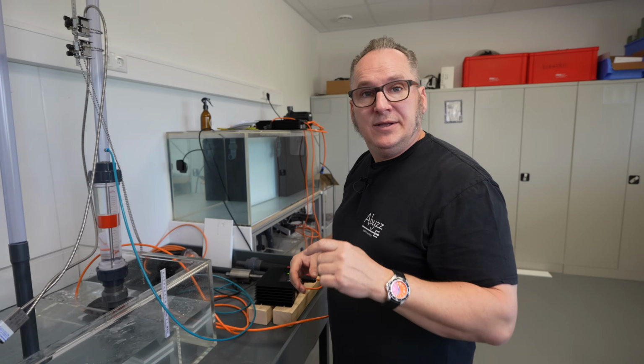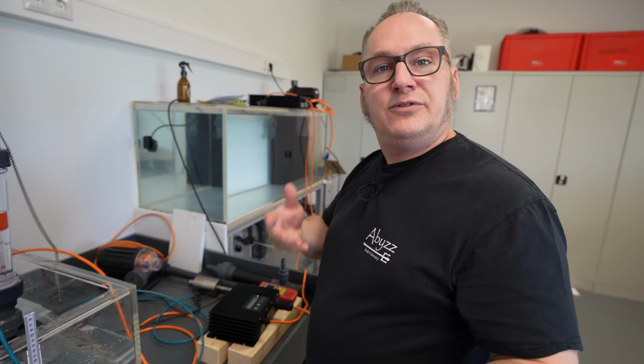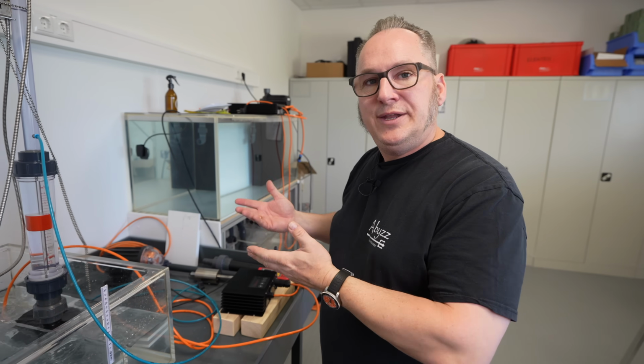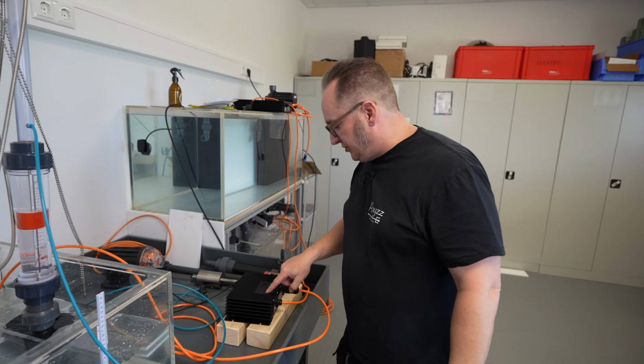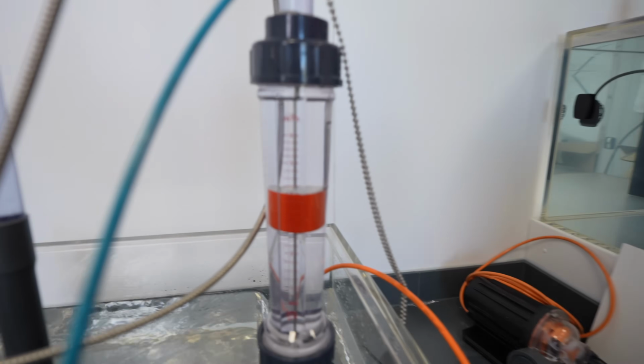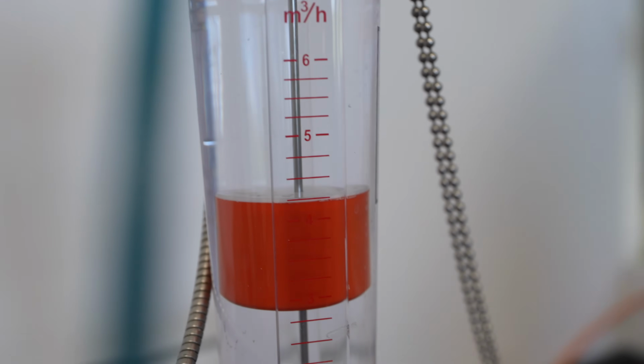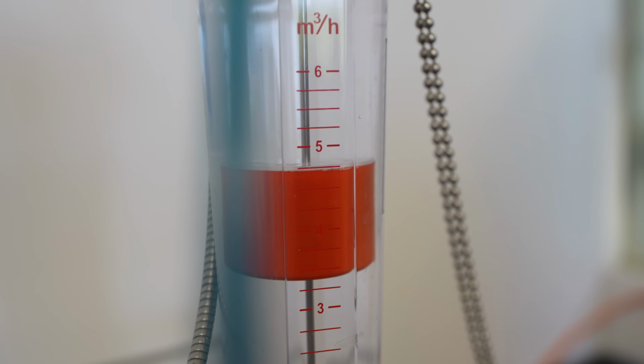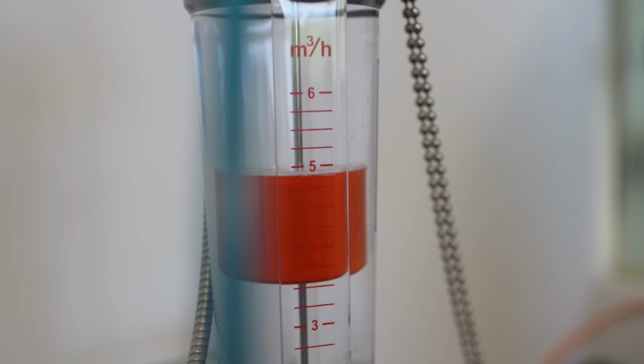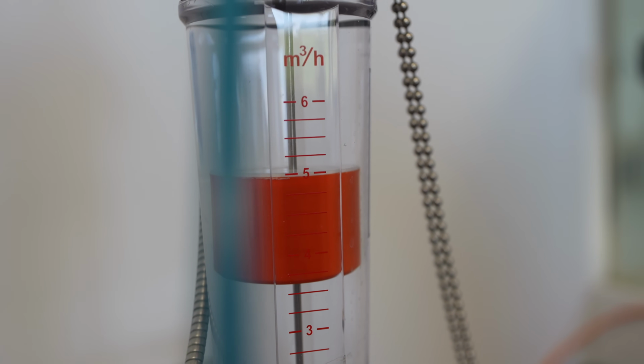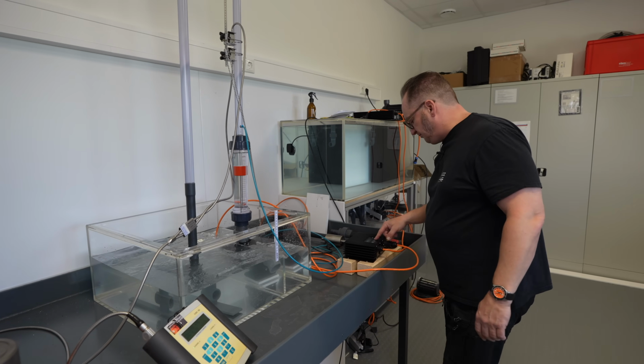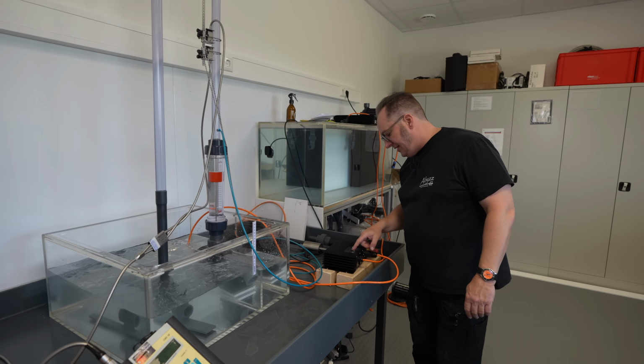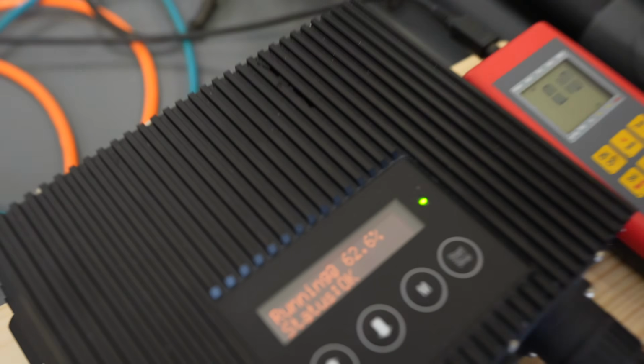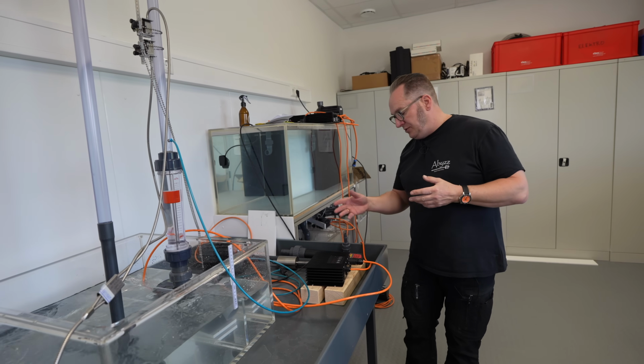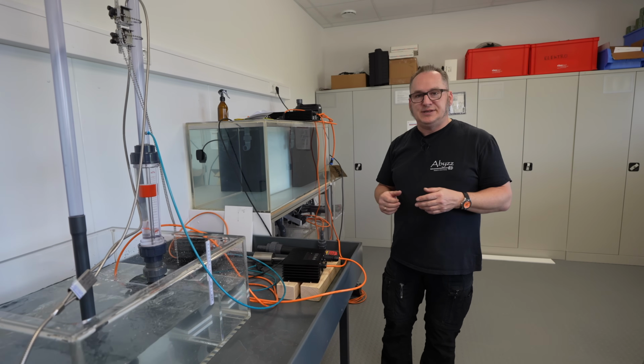Let's first try to reach those 5 cubic meters again to give you an idea of how much more energy you have to invest now to reach the same turnover rate. So we're dialing this up, and you'll see the measurement device go up. So now we are at 5, I would say. That shows 5.2. So we are at 83 watts. In the first place, with the first plumbing, it was 49, and now we are at 82, 83. We'll wait for the reading in just a second.